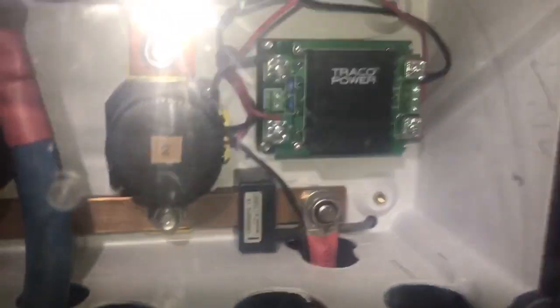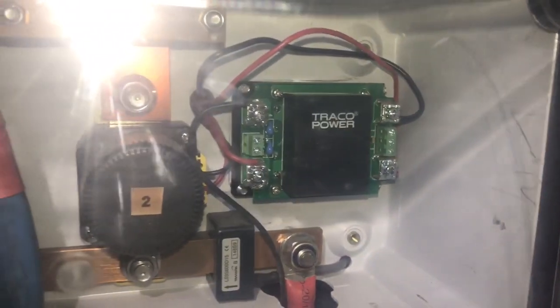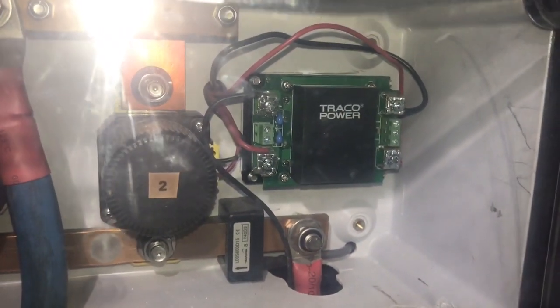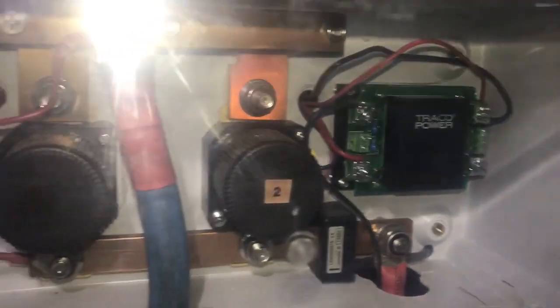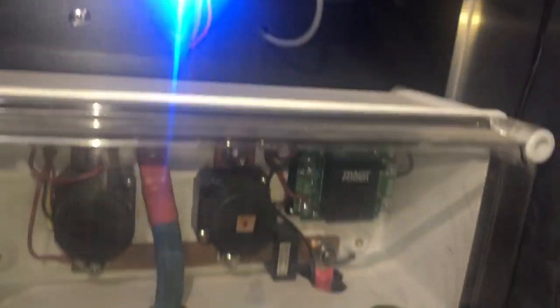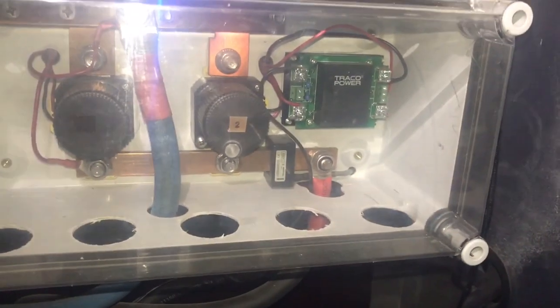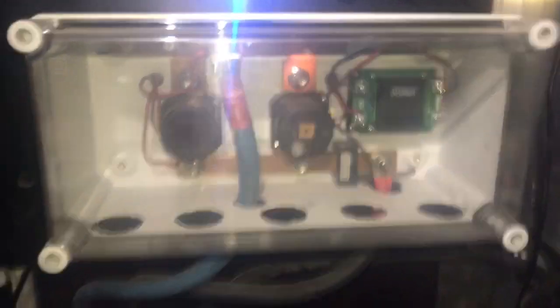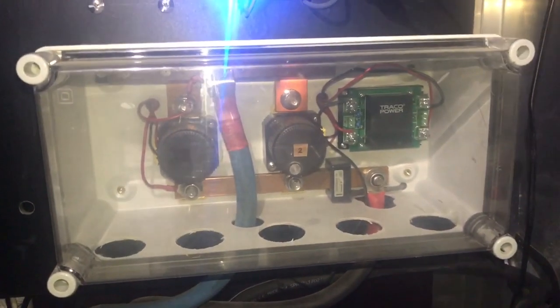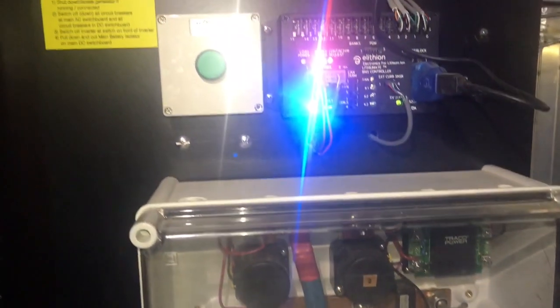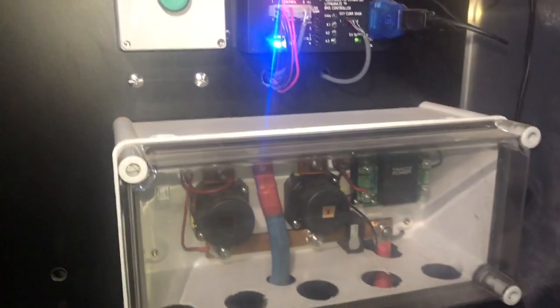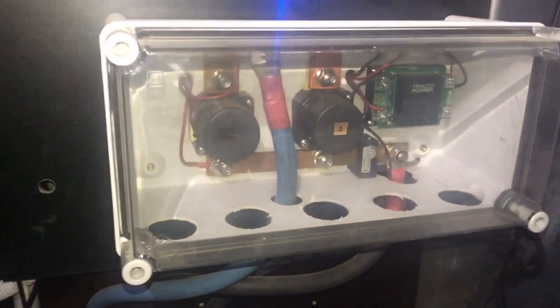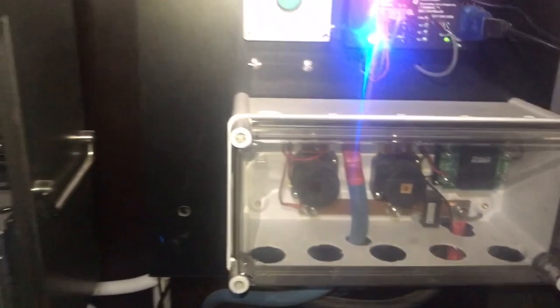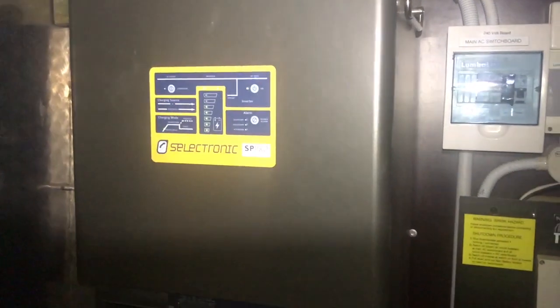This is a 12 volt supply that's also connected directly into the battery system. So even when the inverter is off, the BMS is powered directly from the 12 volt supply coming from the battery system. The circuit diagram for this is on the E-lithium website, and it works reasonably well. The downside, if you will, is that as soon as these contactors go, the whole system goes down, because this electronic box relies on an always-on battery.